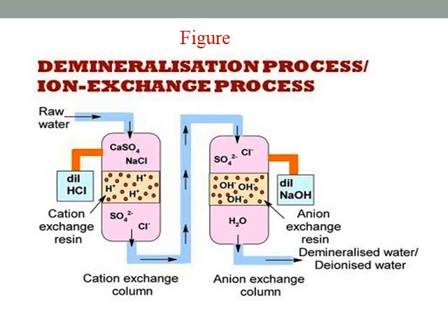Now, the water which comes after the cation exchanger is passed through an anion exchanger. The anion exchanger will exchange only the anions but not the cations. So anions like chloride, sulfate, carbonate, and fluoride will get exchanged with the anionic exchanger bed. This anionic exchanger bed consists of the polystyrene polymer, which is dispersed with some basic functional groups. You know very well that basic functional groups are able to release OH minus and exchange all the anions.